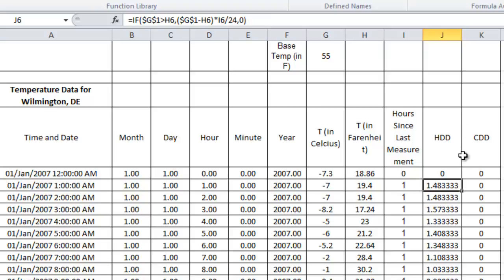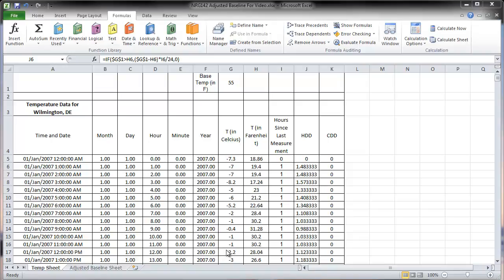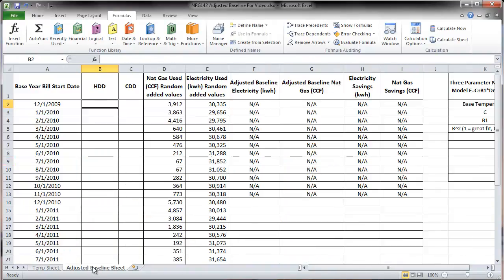Cooling degree days is similar, except the IF statement is flipped, because you don't want cooling degree days when the base temperature is greater than the outside temperature. We'll learn about adjusted baseline in the next part of the video.